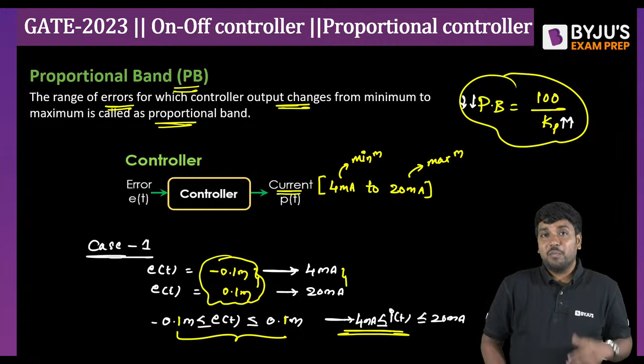Clear? So what happens here is, suppose we increase the value of Kp so much, naturally the proportional band will reduce. If the proportional band keeps reducing, even for minus 0.1 meter you will see 4 milliampere, and for plus 0.1 meter you will see 20 milliampere. So the operating range of error for the controller is very, very narrowed down. And that leads to a very important controller, that is the on-off controller. Clear? But let me show you the practical illustration, then you will understand better.